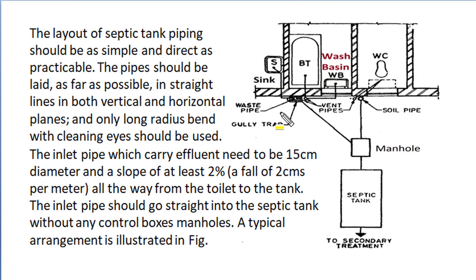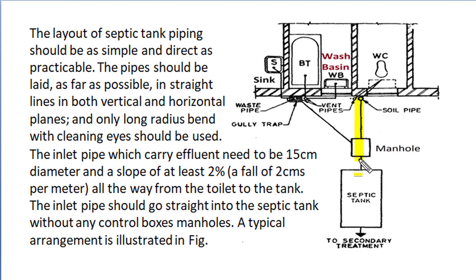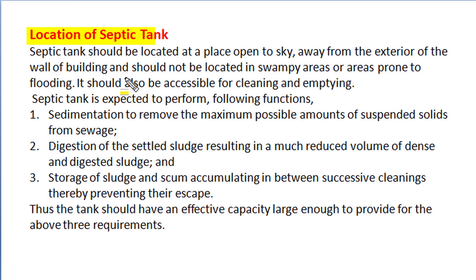The layout of septic tank pipe lining should be as simple and direct as practically possible. The pipe should be led as far as possible in straight lines both in vertical and horizontal planes, and if bends are required in pipe lining, only long-radius bends with cleaning eyes should be used. The inlet pipe which carries effluent needs to be at least 15 cm diameter, and the slope of the inlet line should have at least 2% gradient — that means a fall of 2 cm per meter is required all the way from the toilet to the tank. The inlet pipe should go straight into the septic tank without any control box or manhole. A typical arrangement of septic tank pipeline is from water closet, bathtub, wash basin and kitchen sink as shown.